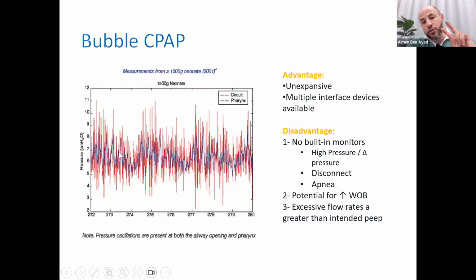In bubble CPAP, you control two parameters. You control the flow and you control pressure. The general recommendation is you keep them the same. I start with PEEP of 5, flow 5; PEEP of 6, flow of 6. But if you have a baby where the bubble is not bubbling very well or who has some respiratory distress, you can leave the pressure and go up in flow. You will generate more bubble, and maybe that helps.